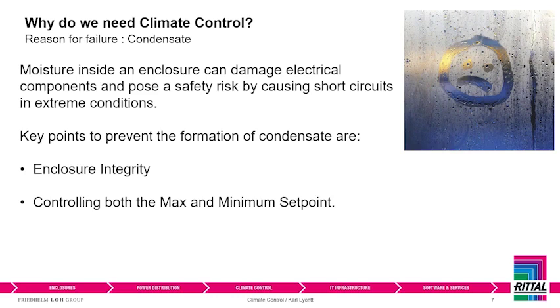As well, say for example you used to use fans and filters and now you've moved to a cooling unit. I have that a lot, where people just leave the fans and filters on, or cover them with cardboard, which is just not going to cut the mustard, I'm afraid. You need to cover or replace those panels properly with steel and really make sure that the ambient air, which is dirty and hot in comparison to inside the enclosure, does not go inside the small ecosystem, the small atmosphere if you like, that we're trying to create inside of the enclosure.